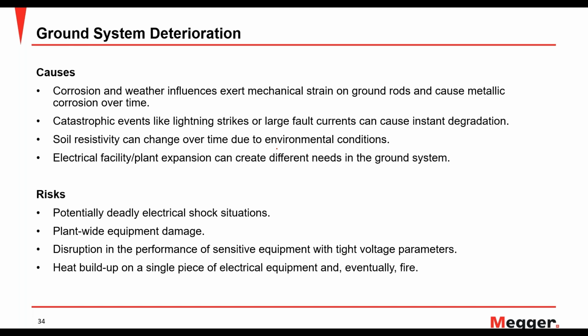And why is it important to test? Because obviously a grounding system is not eternal. It degrades over time. There's usually metallic corrosion or some kind of external mechanical strain that is laid upon the grounding rods or plates. So you have all those different factors playing into the picture, plus any catastrophic events like lightning, storms, or large fault currents that can cause an instant degradation of your grounding scheme. So it's very important to test those.